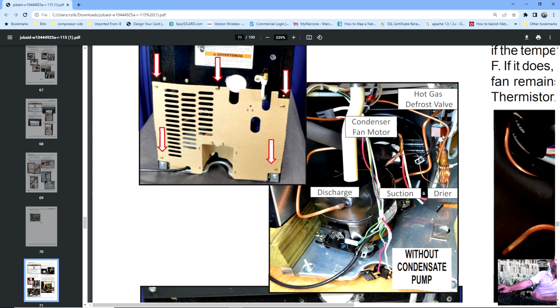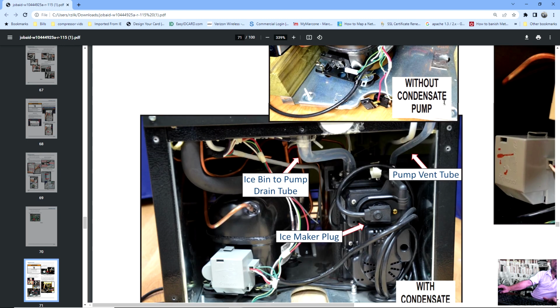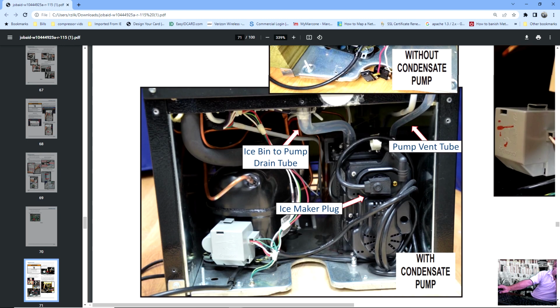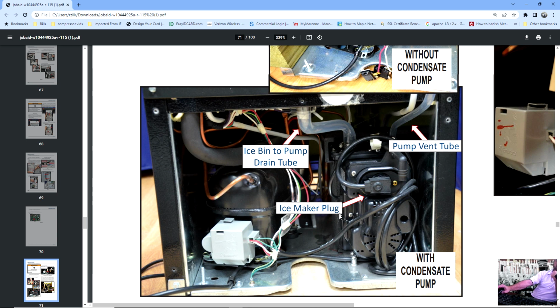Here you can see the hot gas valve. You'll be able to see that from the front or back. This is the valve again that lets the refrigerant bypass the condenser and run straight to the evaporator for ice removal. Now you notice it says without condensate pump. This is called a condensate pump, and on the last page I have a picture of the kit. That condensate pump is for if the customer doesn't have sufficient water drainage.